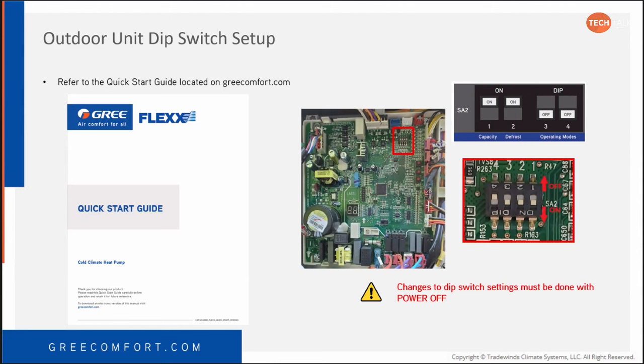What is the default speed setting? We talked about that already. You said 2 and 3 ton is... Well, it's not default. The default is 4, I think. Yeah, for the 2 and 3 ton, it's 4. For the 5 ton, it's 6. 4 and 5 ton is 6.